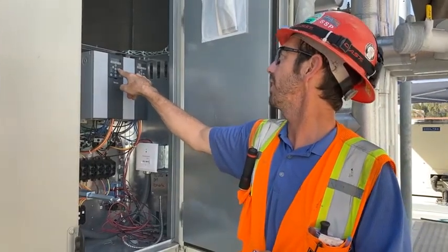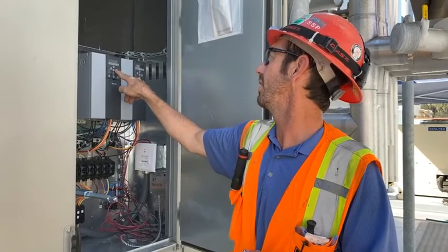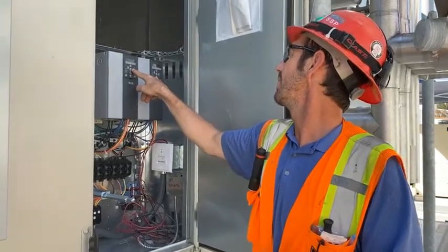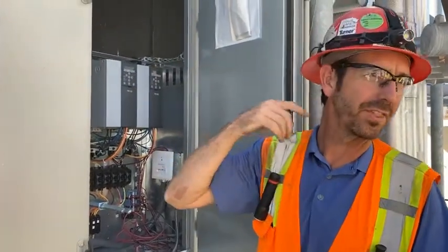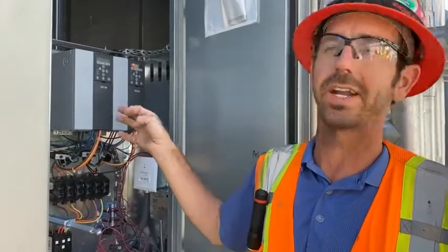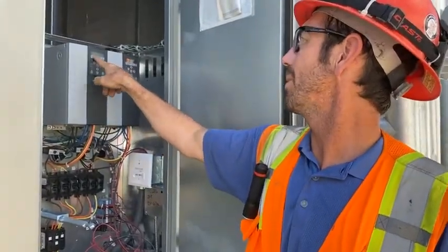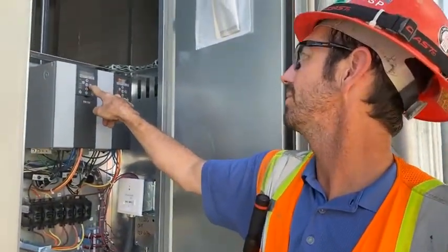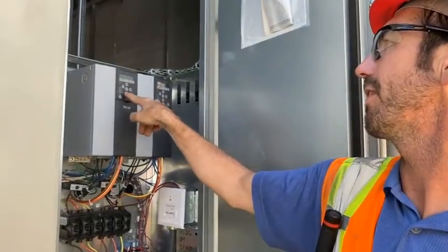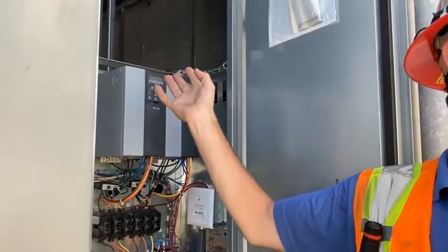If we press over, now the cursor is on one digit at a time. So right now, the last time it was run, it was at 30 hertz. It's going back to 30 hertz right now. So I can change that by moving this cursor over with the arrow. It's highlighted on the 3. If I press down, it's going to go down by 10s. I'm in the 10s digit, okay?